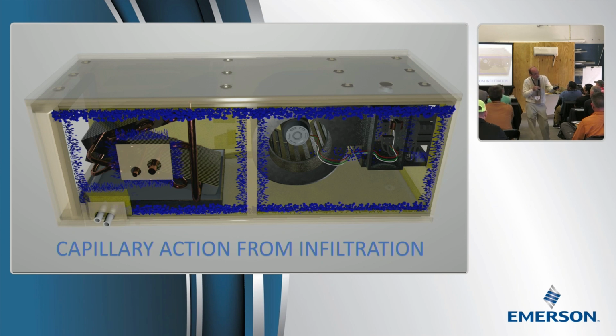So I don't care if you use painter's tape, black tape, or gray tape, but this air is upstream of the coil in this case. It's not leaking in and going through the coil. You're mixing this air in raw. So it isn't doing you any favors inside the house either, much less the sweating duct. So is it ugly? I think it is. I think if you do a pretty installation, the equipment looks better if you don't put the sealant tape on, but it works.